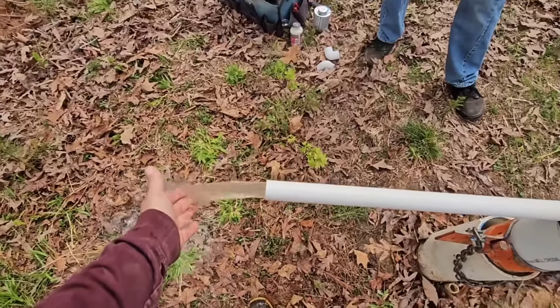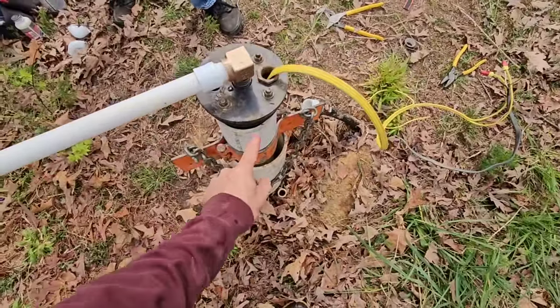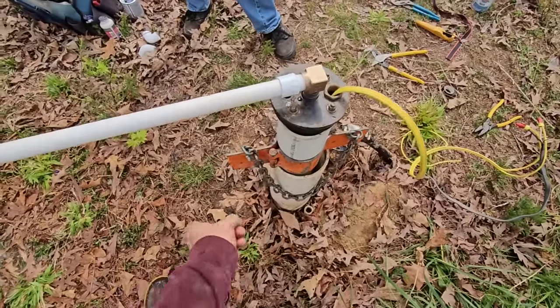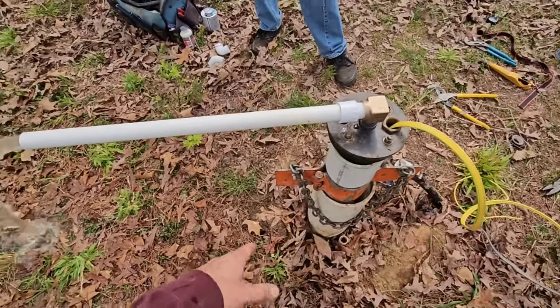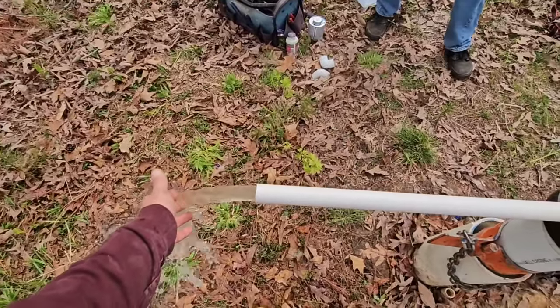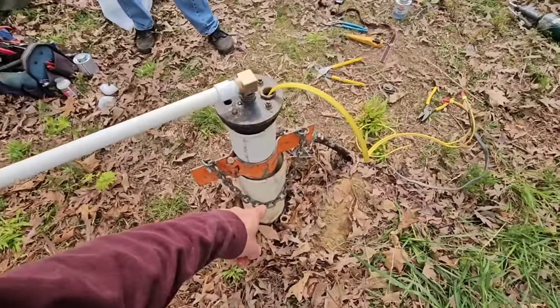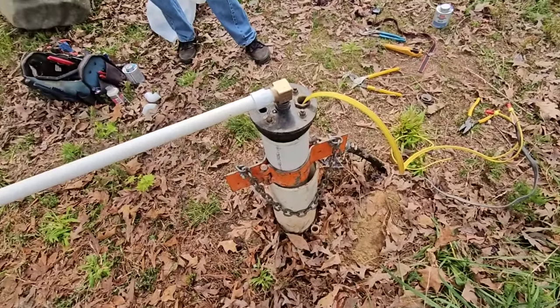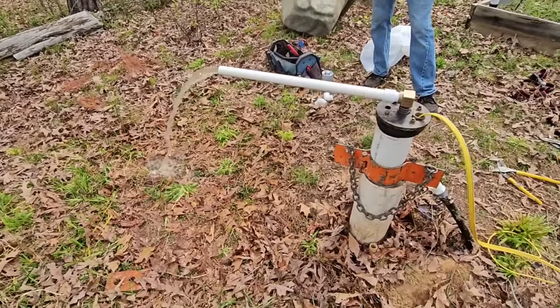We also don't want the well to run out of water, because we pushed the seal down in the well below the 90-foot mark. We don't want the 90-foot zone to be feeding this well all of its water. If we start running the well out of water, then we'll know we cut off its main water supply. Then we'll have to come out here with a crane and grab that chain right there and pull this system out of the ground. That's why we have to test it.